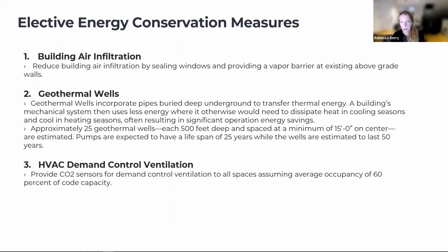You'll see, interestingly enough, geothermal wells listed here as an energy conservation measure when Ken just talked about it as a mechanical system. It is both. So geothermal, otherwise known as water to water heat pumps using the ground as a heat exchanger, is a very efficient system and does bring down your energy use intensity.